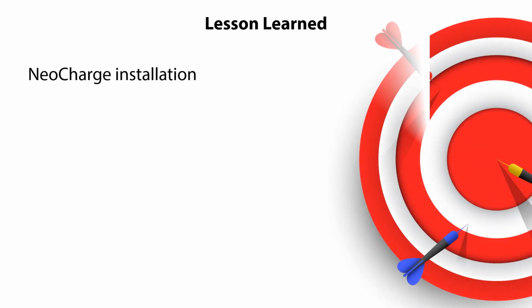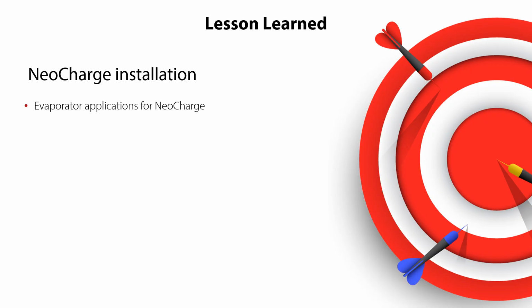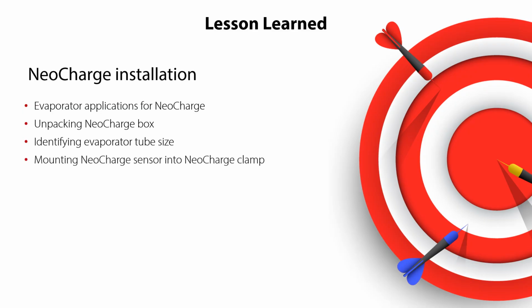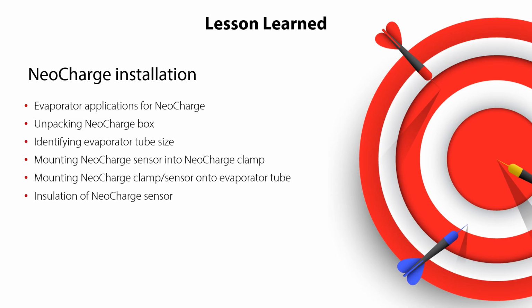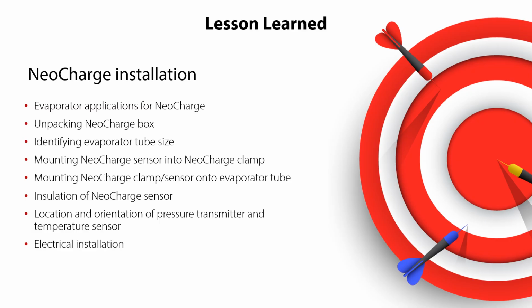So, you have now completed this video about the Danfoss Neocharge installation. This means that you know the evaporator applications where the Neocharge is used. You know how to unpack the Neocharge box. You know how to ensure that the Neocharge clamp will fit to a given evaporator tube size. You know how to mount the Neocharge sensor into the clamp. You know how to locate, orient, and fix the clamp with sensor onto the evaporator tube. You know how to insulate the Neocharge sensor after installation. You know how to locate and orient the pressure transmitter and temperature sensor. And finally, you know where to find information about the Neocharge electrical installation. All this ensuring a safe and energy efficient system operation.